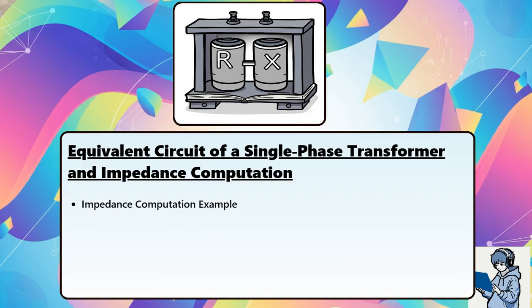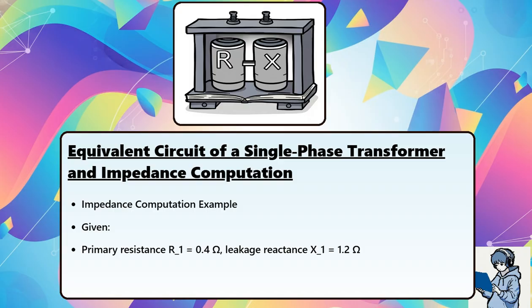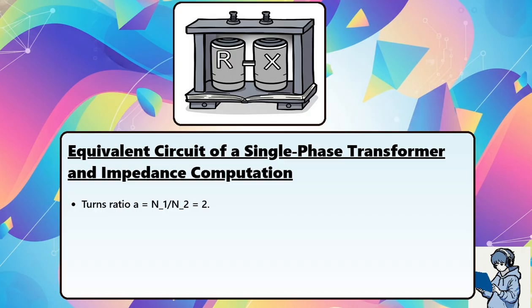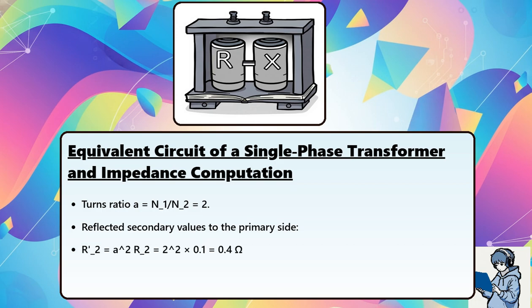Impedance computation example. Given primary resistance R1 equals 0.4 ohms, leakage reactance X1 equals 1.2 ohms. Secondary resistance R2 equals 0.1 ohms. Leakage reactance X2 equals 0.3 ohms. Turns ratio equals 2. Reflected secondary values to the primary side. R'2 equals a squared times R2 equals 2 squared times 0.1 equals 0.4 ohms. X'2 equals a squared times X2 equals 4 times 0.3 equals 1.2 ohms.